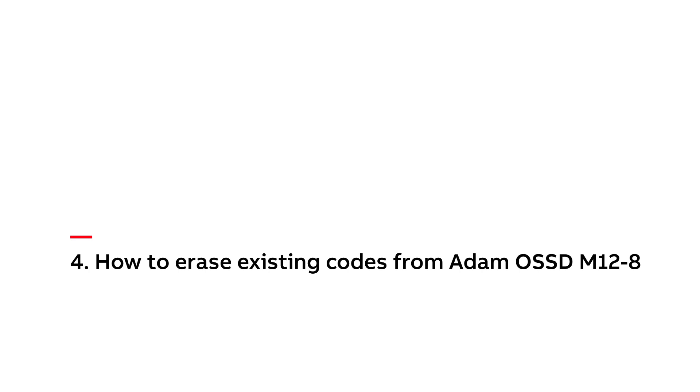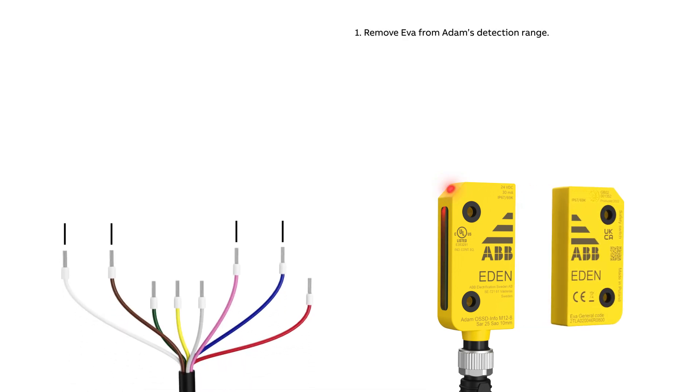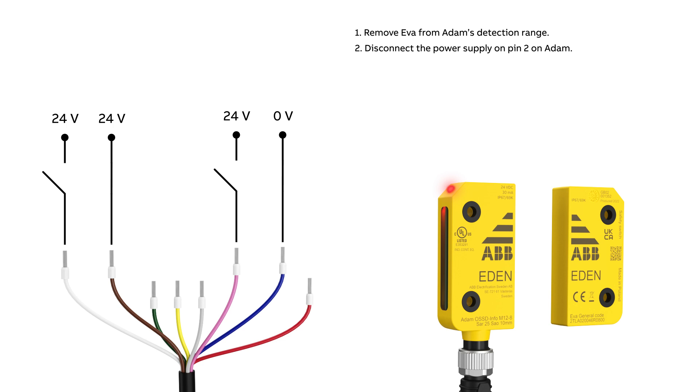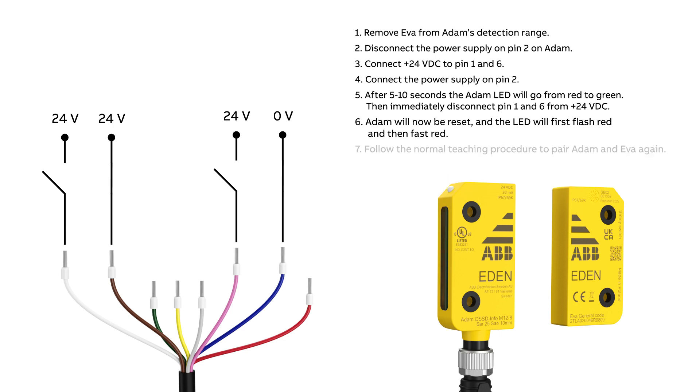How to erase existing codes from Adam OSSD M12-8. Remove Eva from Adam's detection range. Disconnect the power supply on pin 2 on Adam. Connect 24 volts to pin 1 and 6. Connect the power supply on pin 2. After 5 to 10 seconds, the LED will go from red to green. Then immediately disconnect pin 1 and 6 from 24 volts. Adam will now be reset and the LED will first flash red and then fast red. Follow the normal teaching procedure to pair Adam and Eva again.